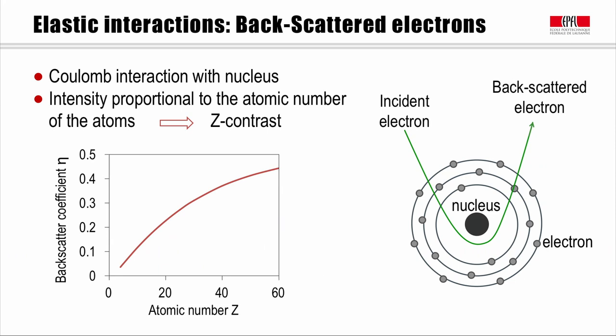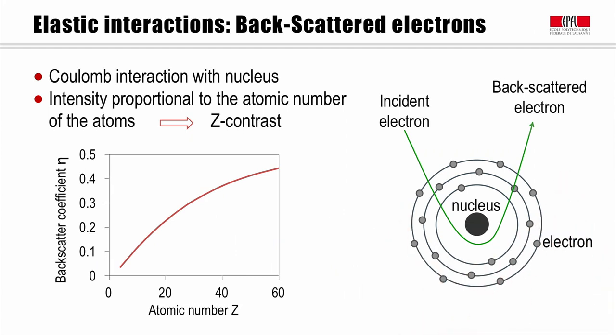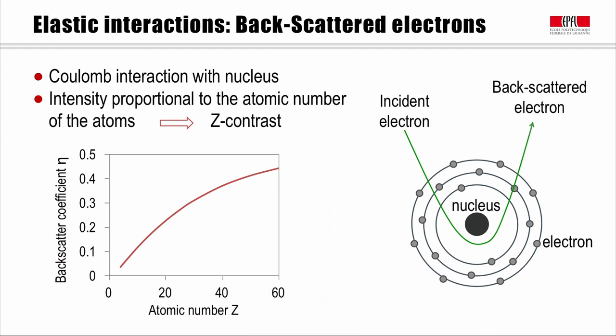Which information can we obtain with backscattered electrons? The Coulomb force with the nucleus increases with the atomic number Z. With the increase of atomic number, the number of positive charges increases, so the incident electron has a higher likelihood of being deviated. If more electrons are deviated, more will be collected, and the contrast will be brighter for a higher Z. This graph shows that brightness increases with atomic number — the backscattered coefficient as a function of atomic number — and a material with a higher average Z will appear brighter because more backscattered electrons are collected.